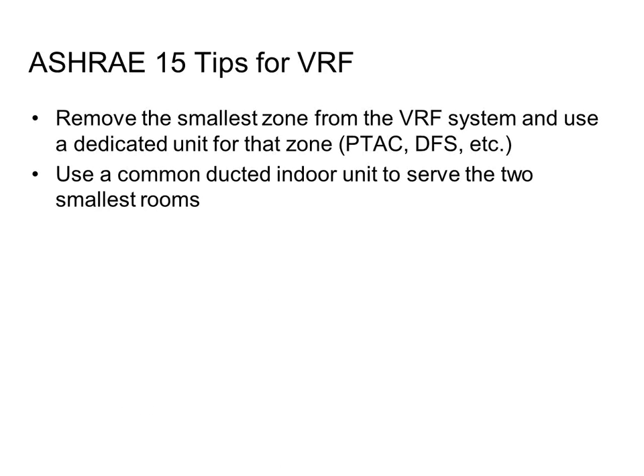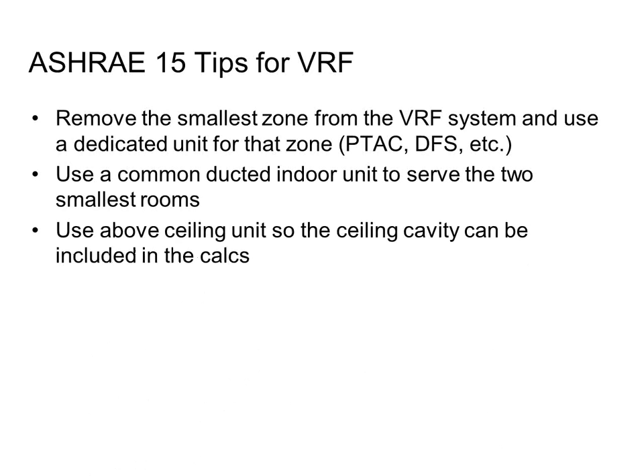So sometimes this makes sense, sometimes it doesn't. If I've got two offices, both on the eastern exposure, and they're both 10 by 10 offices, okay, maybe they can work with one thermostat. But I wouldn't want to mix ones that are opposite exposures, or a conference room with an office or something like that. But I can duct two zones or more to one unit, and then I've increased the cubic volume that I'm thinking about. I can put the unit above the ceiling, right? So putting a unit as a high wall unit on the wall, on a drop ceiling, I have a certain volume of the room. If I put in a cassette style unit, then I have some of my leakage going above the ceiling, some of it going below the ceiling. So I can increase my total volume that I'm looking at. So instead of a 9-foot ceiling, I have an 11-foot to work with or something like that. That may help you if you're right on the borderline.